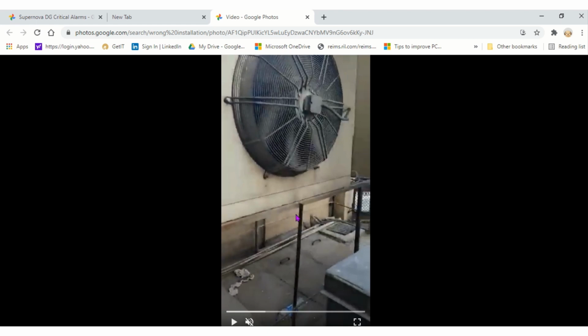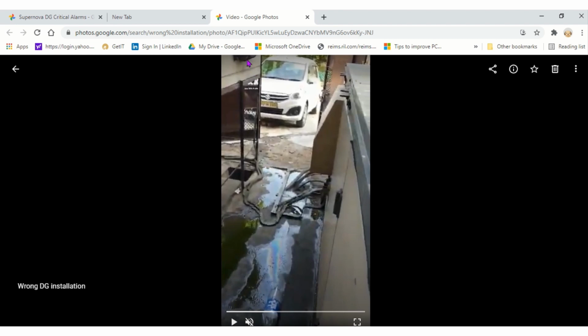If we see here, this air is coming on this side, and this is a fan which is giving hot air in this area. So this air will be going here, here, here, on all the sides, and this is a suction of the DG sets. So if this hot air is going inside this suction part, then as I told you, this hot air cannot properly cool the high temperature coolant. This air will blow through the radiator, but it is not going to cool, because this is not cool air from the ambient. This is hot air which is rejected from the air conditioner.